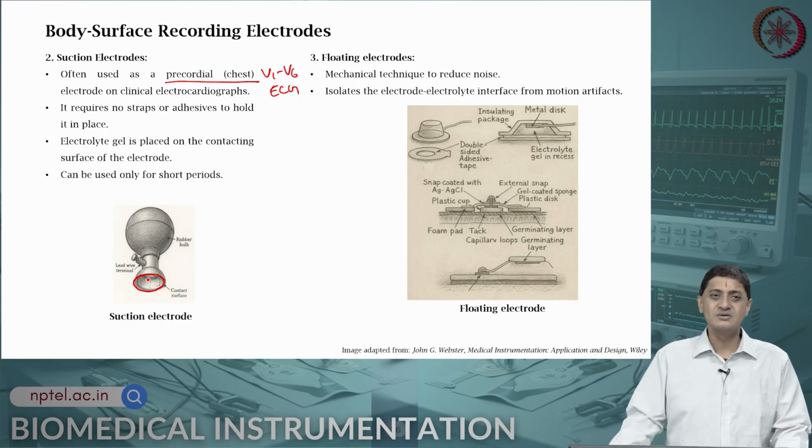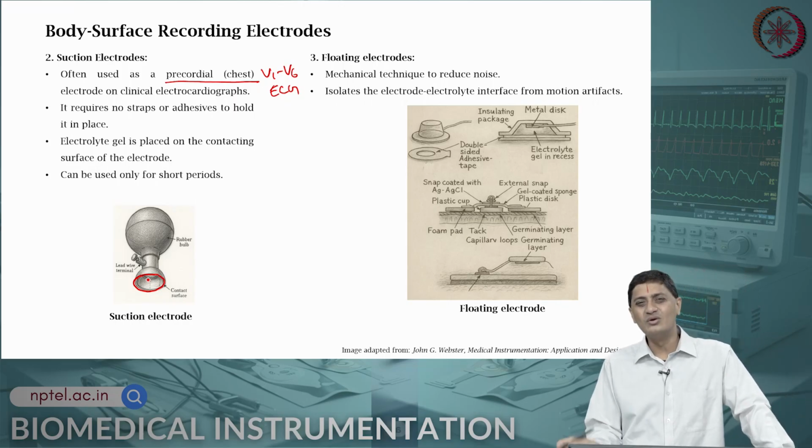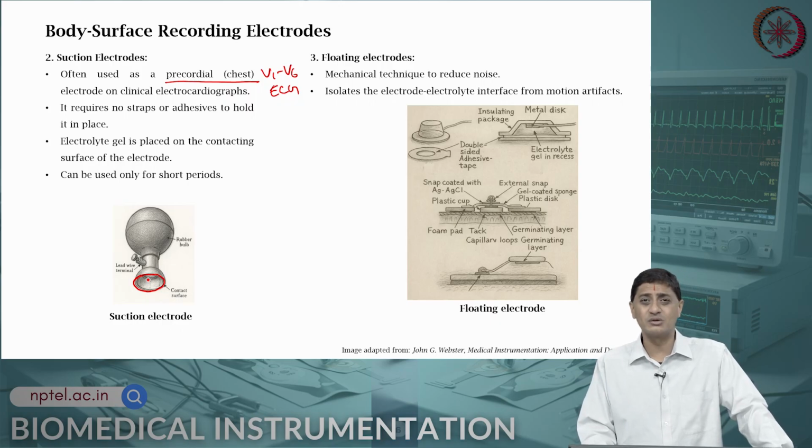Right. So it can, but then the problem is, after some time, a small amount of air will slowly start getting inside, and then it might come off. So it can only be used for short periods of time, only a few minutes. It cannot be used for long term monitoring. We already defined what is long term monitoring. Long term monitoring means several hours to several days.